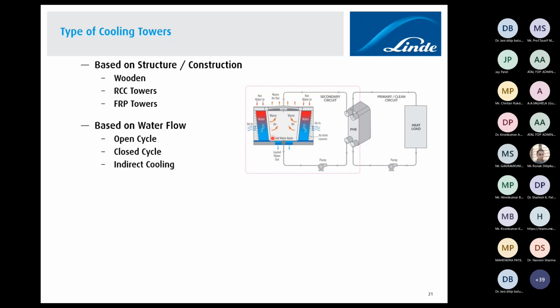you have some constraint on makeup water, because makeup depends on where the industry is situated. Sometimes on a river bank, so you are depending on that particular river water. Sometimes on the seashore, so you are depending largely on desalinated water or a seawater application. That's why. And typically, I have seen in Reliance Industries, it is in a coastal area, so they are using a sea cooling tower. This complete cooling tower is designed to take care of very high TDS, 20,000 TDS. When you send 20,000 TDS, all exchangers cannot take care. But they have a heat exchanger with Incoloy and Monel metal or a noble metal which can easily sustain seawater. Sometimes duplex steel is also widely used.